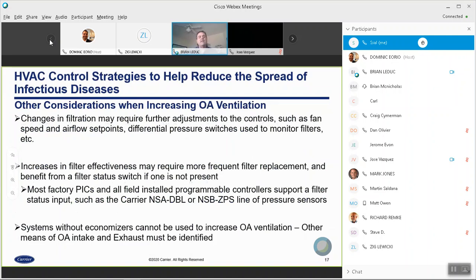Changes in filtration are recommended, but again, you're going to run into limitations in terms of how much filtration a given piece of equipment can tolerate. Again, I've got some slides that I'll get to here that we spoke with the mechanical, or let me rephrase that, we spoke to the equipment guys, the RTU product managers, to get their take on what some of the mechanical limitations are going to be. And you can increase the filtration up to a certain point. Beyond that, your fan's not going to be able to push enough air through the system to properly heat, cool, and ventilate the space. So if the customer does choose to increase filtration, you might need to make an adjustment to the differential pressure switches that are in place.